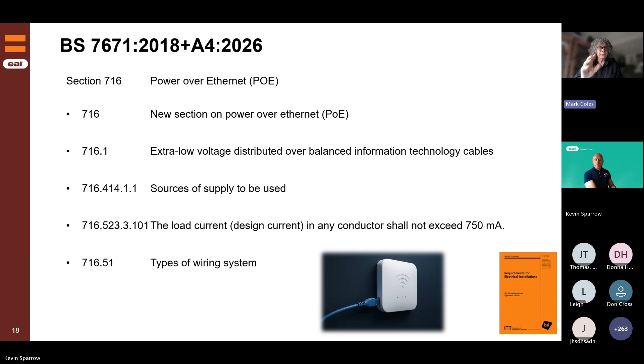Clipping cables, essentially it's in the SELV and PELV area. It's extra low voltage, and in 7671 in Part 2, you'll see we've got Band 1, Band 2 circuits. Band 1 circuits are up to 50 volts AC, 120 volts DC, and Band 2 is everything after that, up to 1000 volts AC, 1500 DC. So we've always had requirements for the cabling and the installation, and the TV installers that come and put the dish on your house and cables, the cables they install, they should be following BS 7671. We just haven't got involved in the ins and outs of what's been sent or broadcast in terms of the data side of things, and we won't. Other than in 444, we haven't got to corrupt the signal, of course, but that's something else. Touched on that earlier. But yes, it's about the Power over Ethernet.